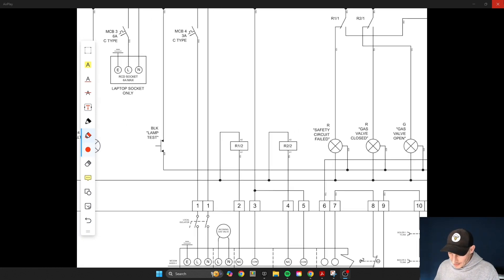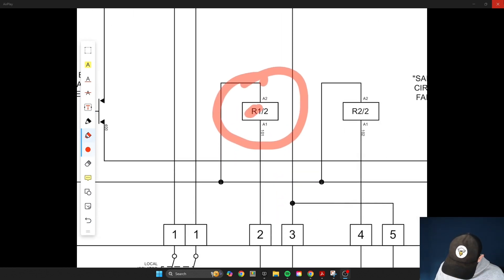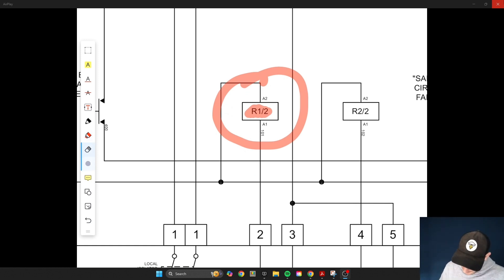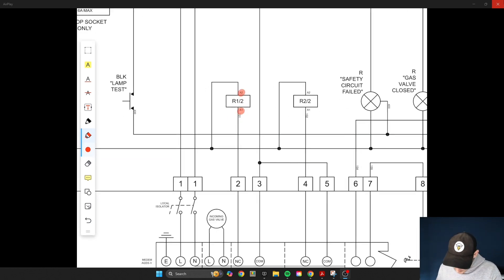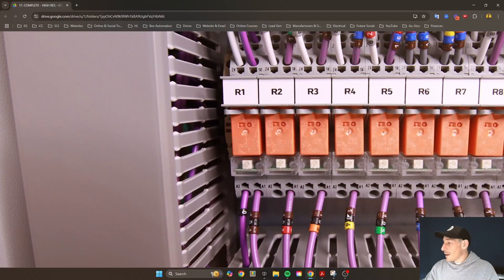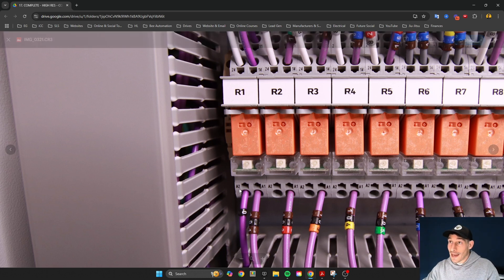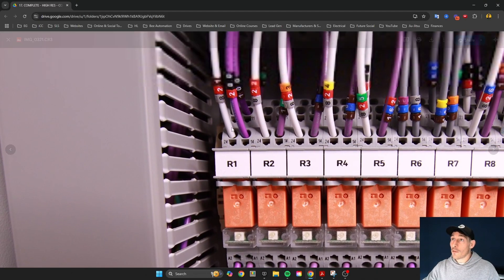You'll always see on any type of schematic that there are two parts of a relay. The first part is the coil part of the relay, and you can see it's labeled R1/2 — relay 1, and I'll get into what the slash 2 means later. On the coil side of a relay you'll always have A1 and A2. The A1 side is always connected to the positive terminal, and A2 is always the negative terminal.